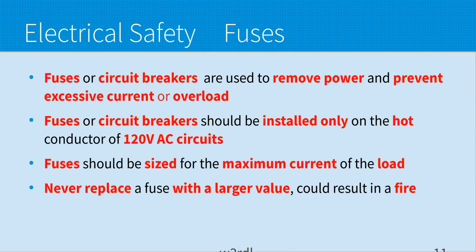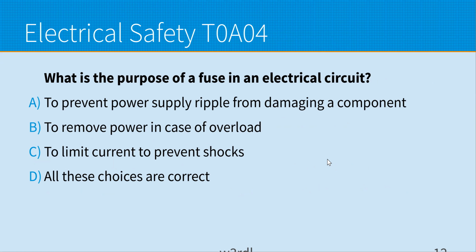You never want to put in a fuse or a circuit breaker that has a much higher current rating than the load that you're supplying. So in the case of a piece of equipment with a fuse in the back that says it's rated for 5 amps, you probably don't want to put in more than a 5, maybe a 6 amp fuse, certainly not a 10 or 20 amp fuse. Something else inside will burn up first, but not the fuse. And then you get a fire, the smoke detector goes off, and the fire department comes.